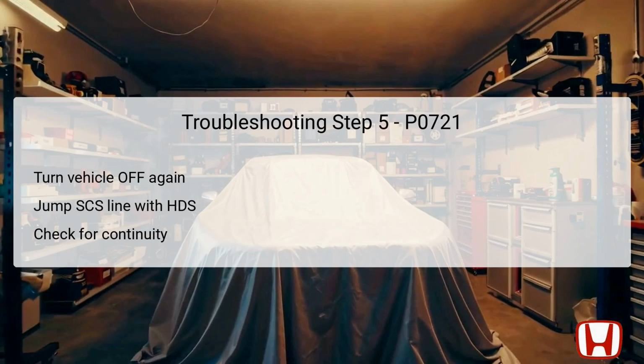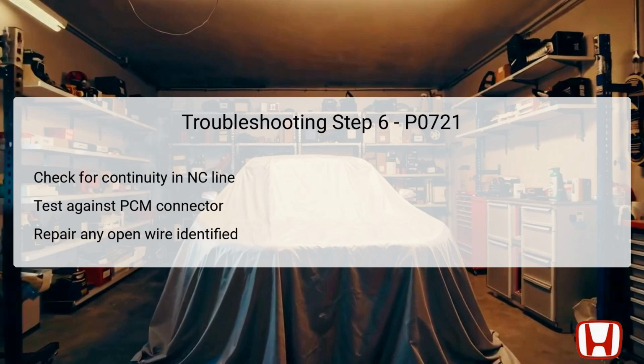A successful reading of 1 MΩ or more verifies that the NC wire is not shorted. If this reading is confirmed, proceed to the next troubleshooting step. If the measurement shows continuity, it indicates a short in the NC wire, requiring you to locate and repair the fault in that wire. In the final troubleshooting step, step 6, you will check for continuity between the NC line and the PCM connection for a clear understanding of the system's integrity.